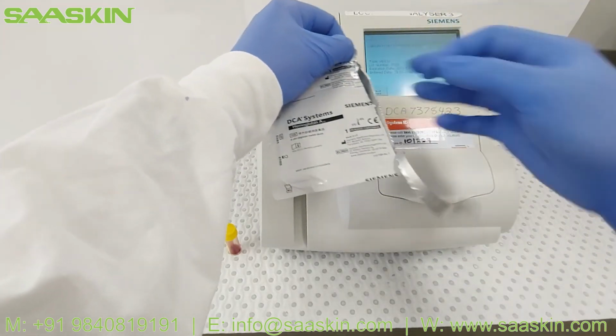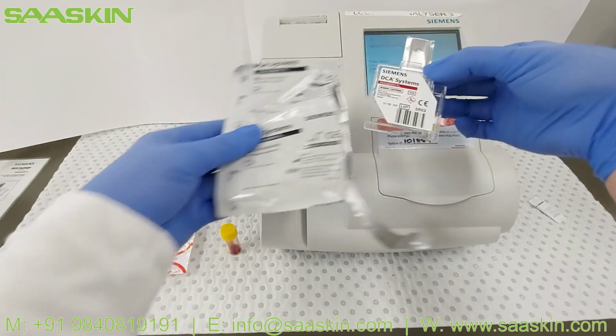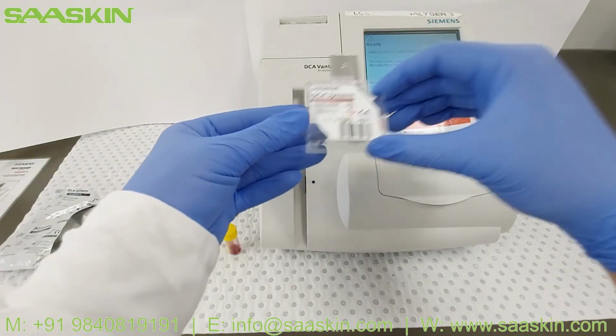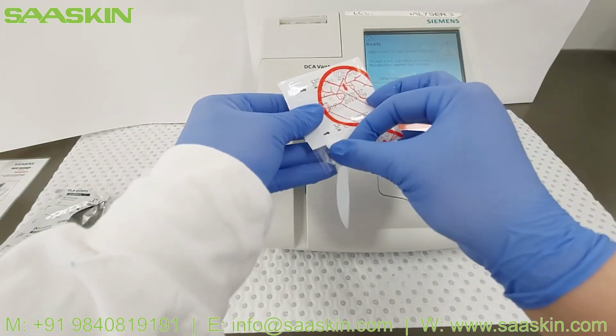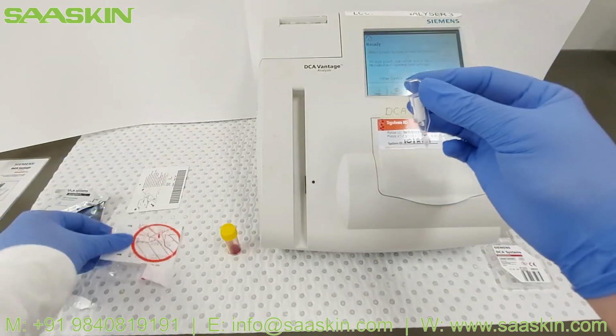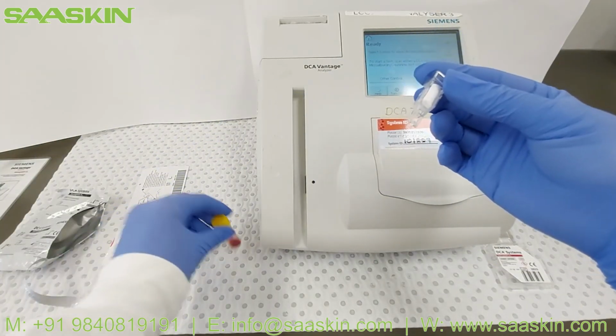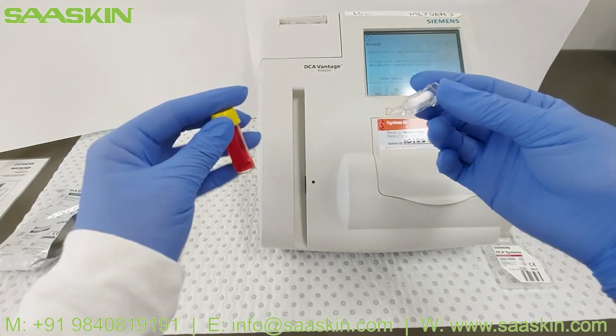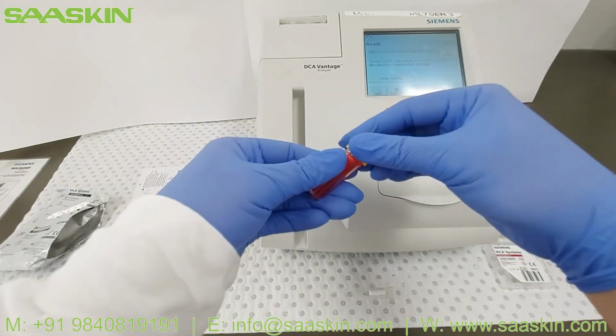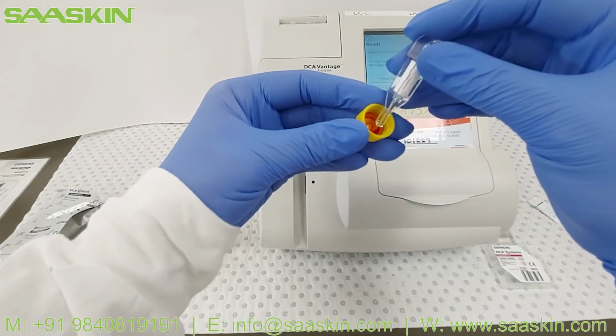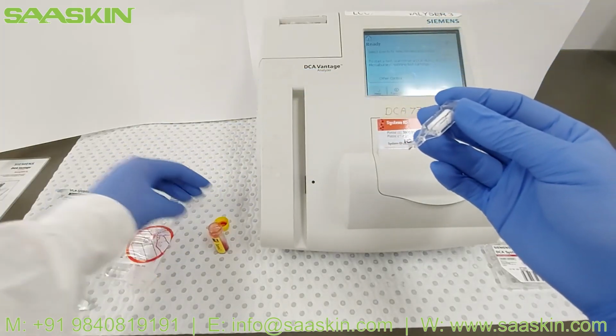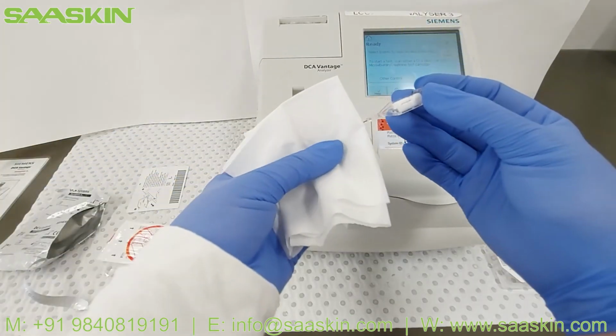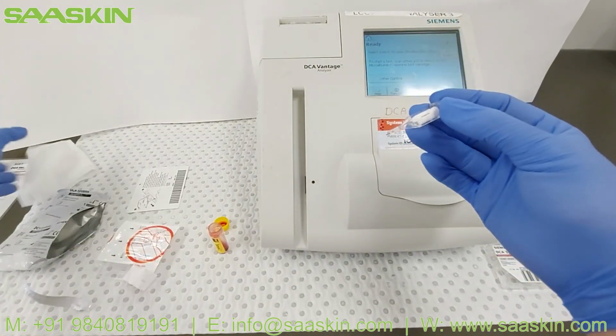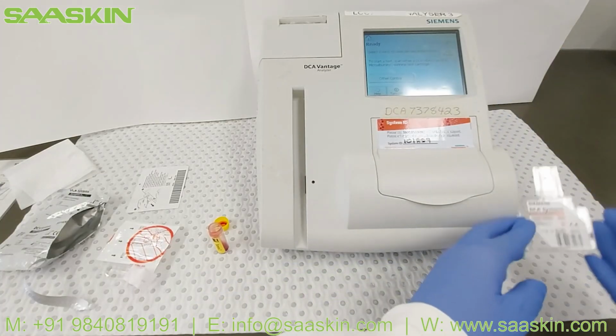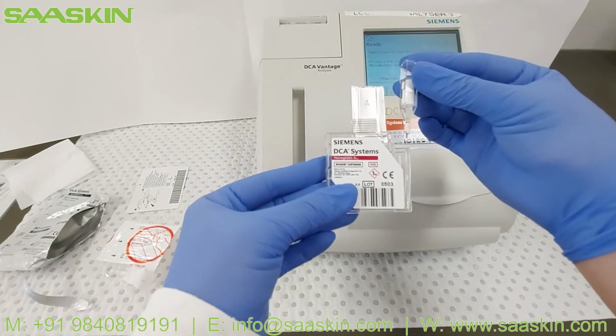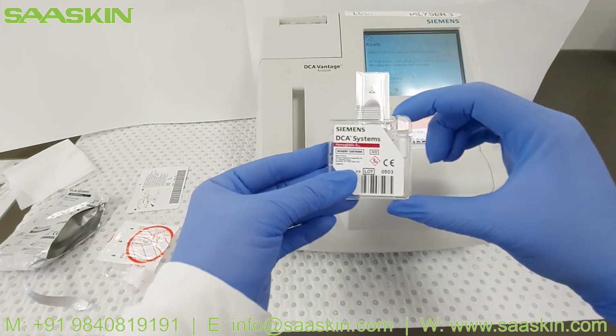Next, open the reagent cartridge package and set to one side. Open the sample capillary packaging by peeling the cover off, careful not to press on the middle of the capillary as it may snap. Use anticoagulated sample and invert multiple times before using the blood in the lid to fill the sample capillary. Use a tissue to wipe the outside of the capillary of excess blood. Orienting the upper curved edge of the capillary outwards, snap the capillary into the reagent cartridge.